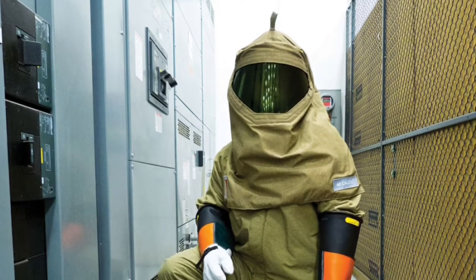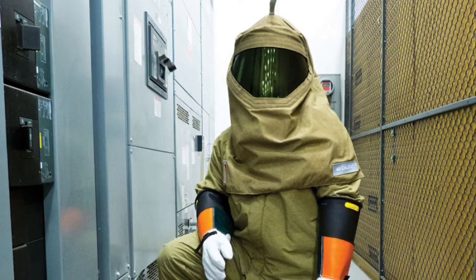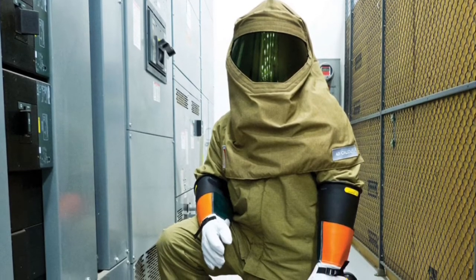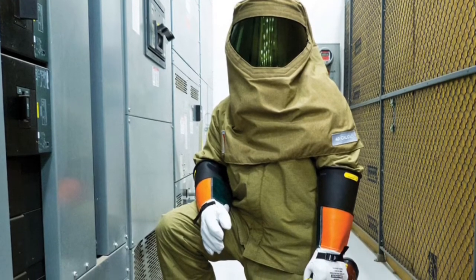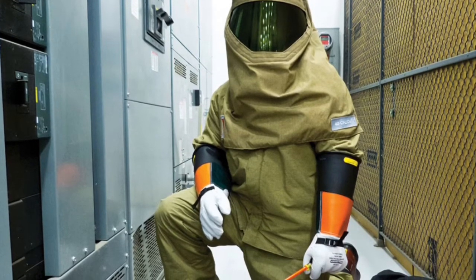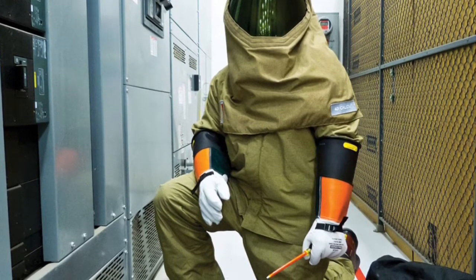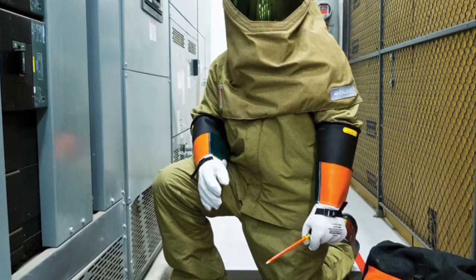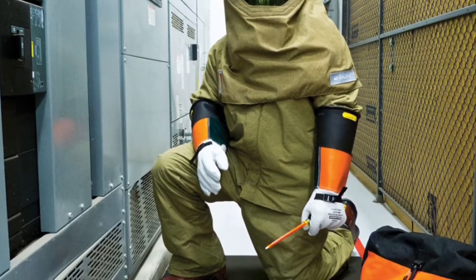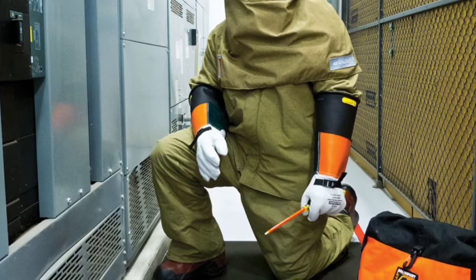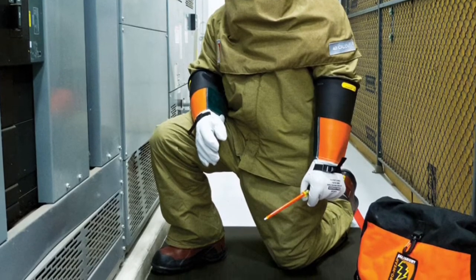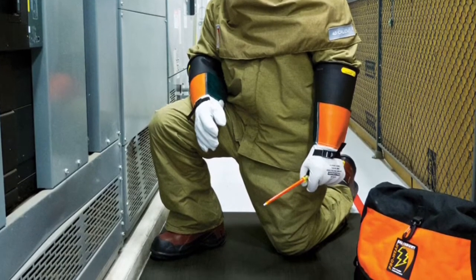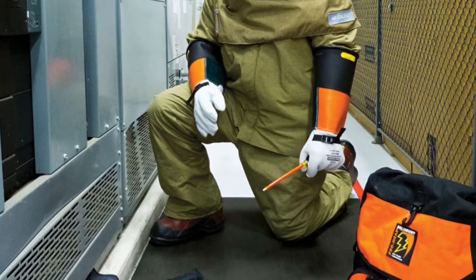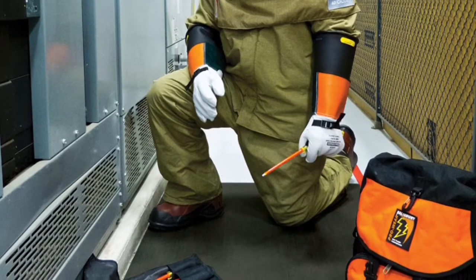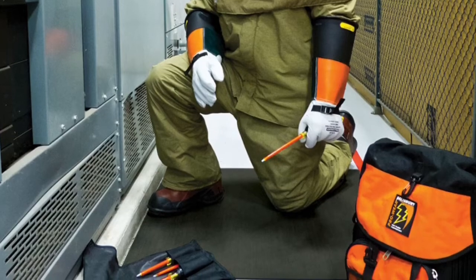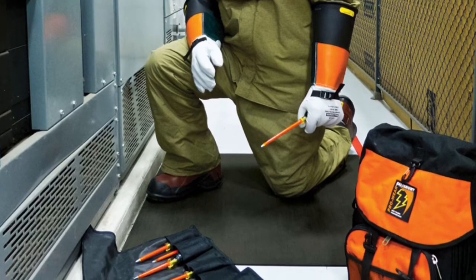An arc flash suit is a complete arc-rated clothing and equipment system that covers the entire body except for the hands and feet. Hands and feet must be covered by adequate arc fault protective equipment as shown in the picture. Employees shall wear rubber insulating gloves with leather protectors where there is a danger of hand injury from electric shock due to contact with exposed energized electrical conductors or circuit parts. Employees shall wear rubber insulating gloves with leather protectors and rubber insulating sleeves where there is a danger of hand and arm injury from electric shock due to contact with exposed energized electrical conductors or circuit parts.